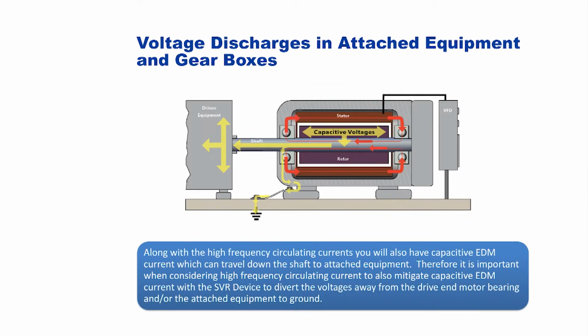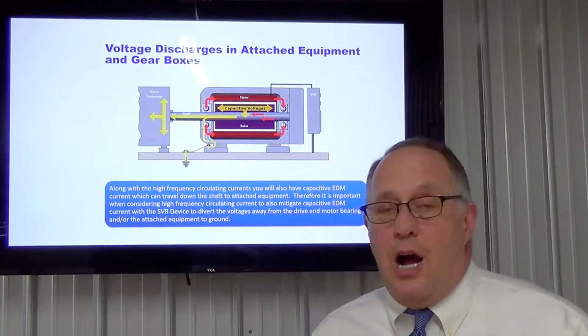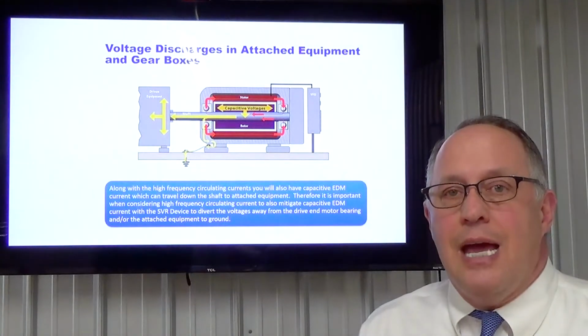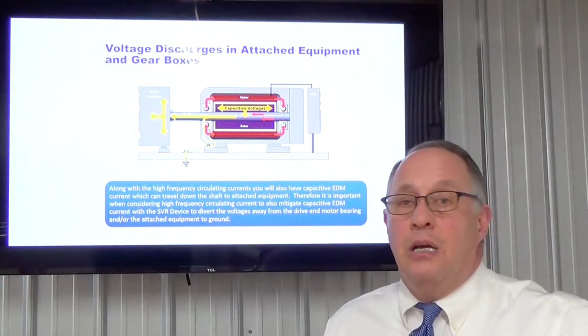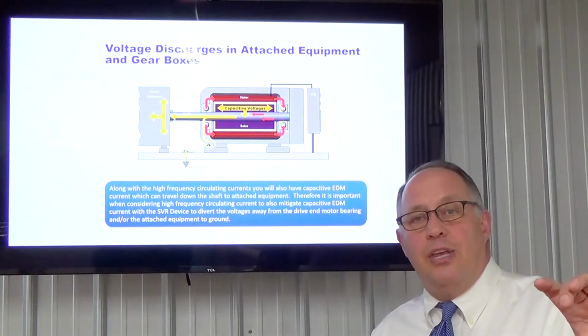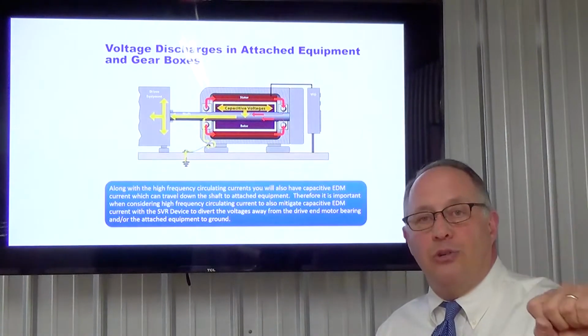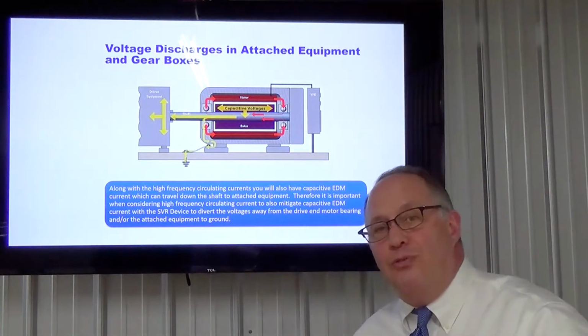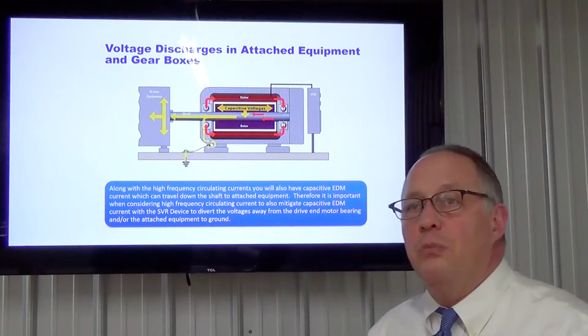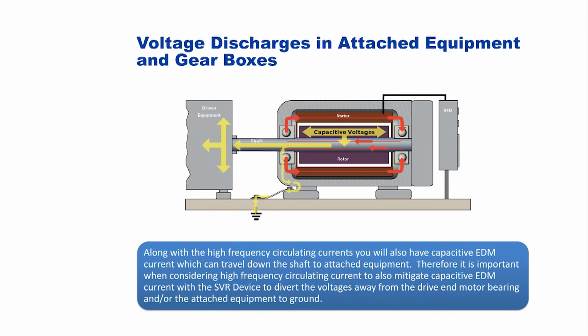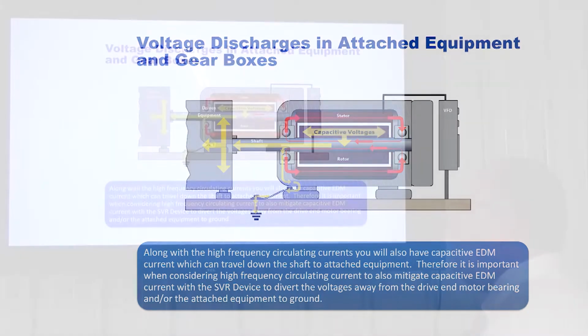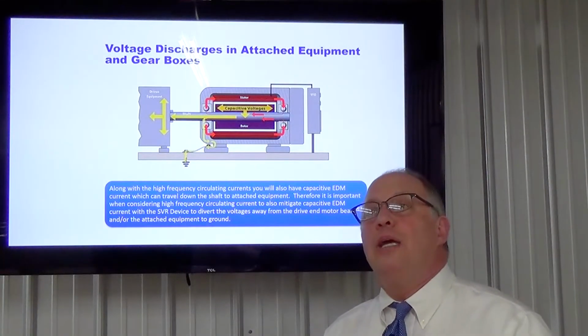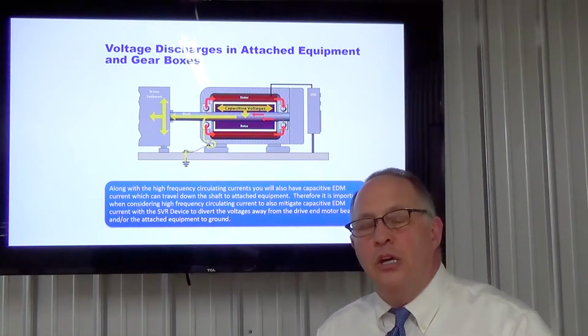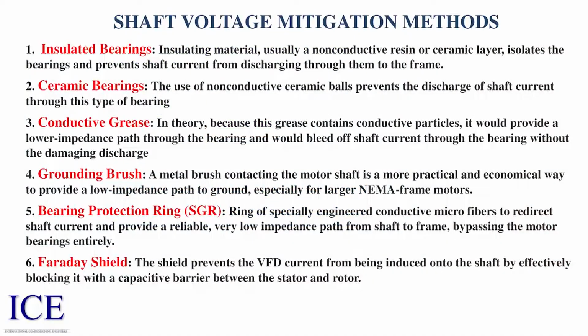Voltage discharge in attached equipment and gearboxes. Well, it would be common to understand that if we've got a voltage on the shaft, it also connects to driven pieces of equipment that usually can have bearings associated with them or be attached to direct drive, which means that voltage will find a place to discharge as well. So you could end up damaging driven equipment as well as the motor. Along with the high-frequency currents, you may also have capacitive EDM currents, which travel down the shaft to the attached equipment. What we need to do is come up with a method to divert that voltage to ground so that we don't get damage with these arcing currents.